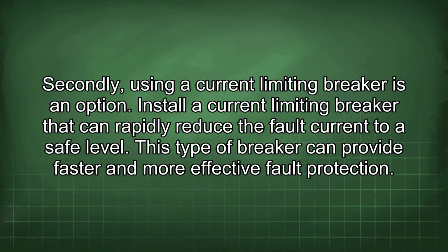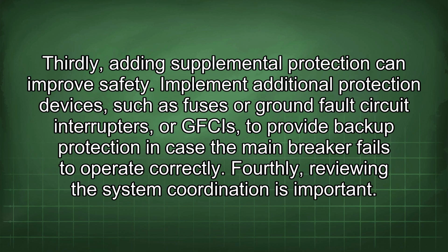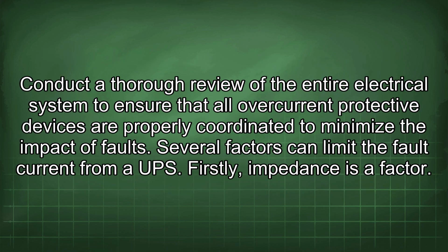Secondly, using a current limiting breaker is an option. Install a current limiting breaker that can rapidly reduce the fault current to a safe level. This type of breaker can provide faster and more effective fault protection. Thirdly, adding supplemental protection can improve safety. Implement additional protection devices such as fuses or ground fault circuit interrupters, or GFCIs, to provide backup protection in case the main breaker fails to operate correctly. Fourthly, reviewing the system coordination is important. Conduct a thorough review of the entire electrical system to ensure that all overcurrent protective devices are properly coordinated to minimize the impact of faults.